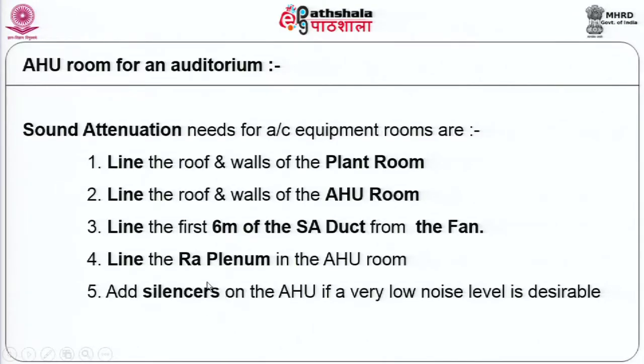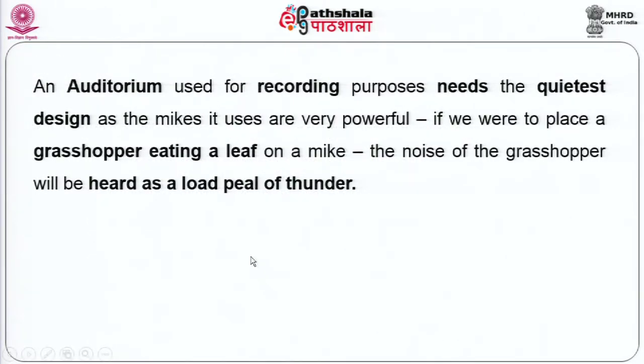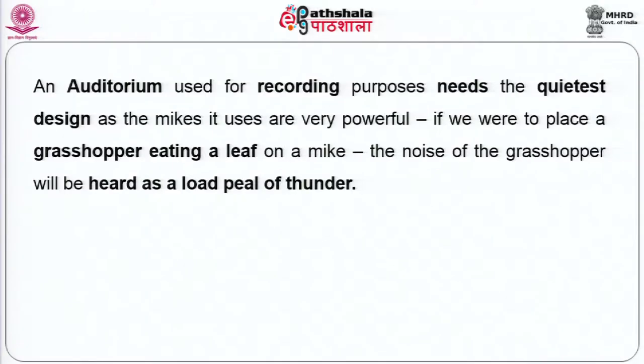Now, if this does not meet the requirement, that is, if you have landed up with equipment which is still noisier than what you expect it to be, there is special equipment available, like silencers, which one can put into the circuit. Now, these were parameters and numbers which I mentioned for a normal auditorium, which is what you would see in most of the service buildings, most of the high-rise buildings. But should you be stuck with an auditorium which requires reduced noise levels, then those types of auditoriums are used for recording purposes and they become extremely difficult to work on because they carry within them mics. These mics today are so powerful that if one were to put a grasshopper on the mic and give it a leaf to eat, perhaps in a normal ear, you and me would never hear that noise, but on the mic, this noise would be like a thunder and you and me would have to run out of the place as we would not be able to bear the noise.